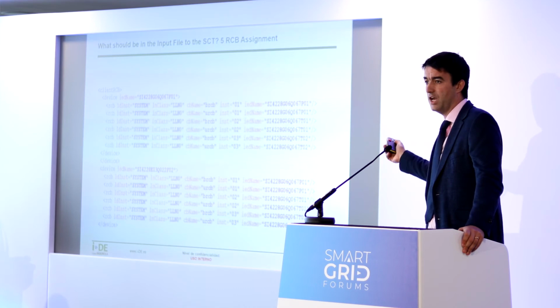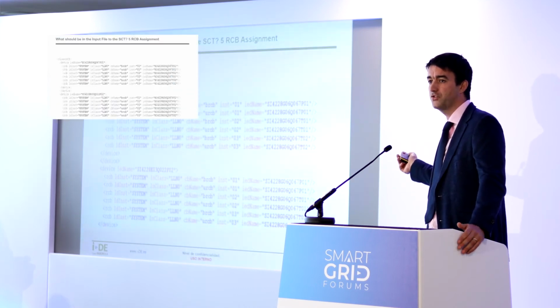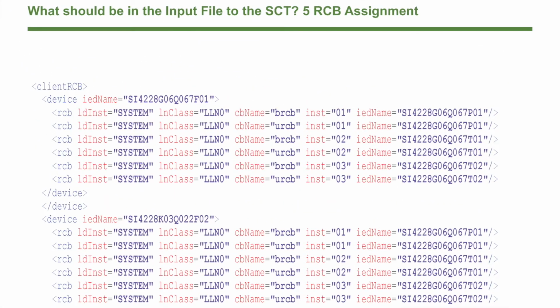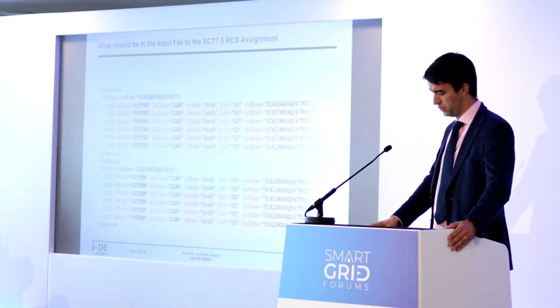We also have something similar, another matrix for the report control block assignment, where for every server IED we have the source block with the IED name, then the identifiers of that report control block, and then the client IED name to which it should be sent.